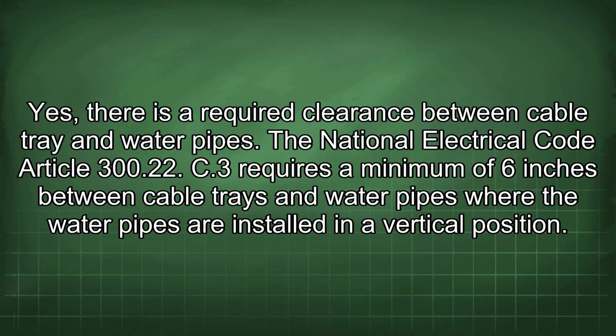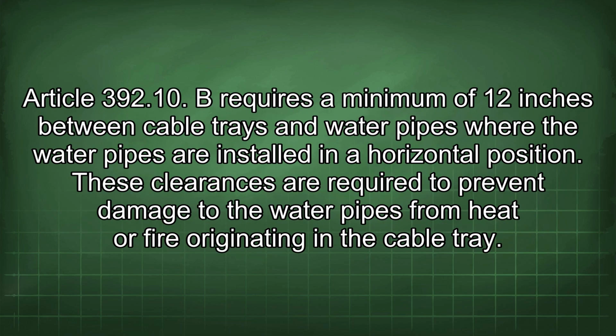Yes, there is a required clearance between cable tray and water pipes. The National Electrical Code Article 300.22 C3 requires a minimum of 6 inches between cable trays and water pipes where the water pipes are installed in a vertical position. Article 392.10 B requires a minimum of 12 inches between cable trays and water pipes where the water pipes are installed in a horizontal position.